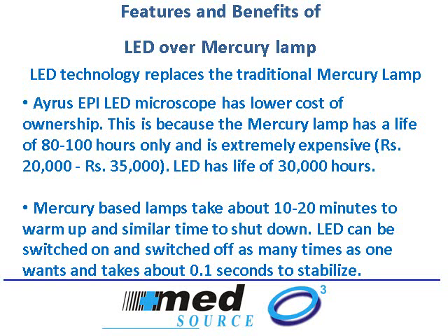Basically, LED based fluorescent microscopes have four major advantages over mercury lamp. First, for a microscope like Ayrus EPI, the cost of ownership is very low. This is because even if the microscope itself is slightly more expensive than mercury lamp based fluorescent microscopes, it has almost zero running costs. On the other hand, mercury lamps have a life of about 100 hours and every 100 hours of use you will change these lamps. One lamp will cost you at least $500 to $600 or 30 to 35,000 rupees. So basically every 100 hours of use you are changing the mercury lamp.